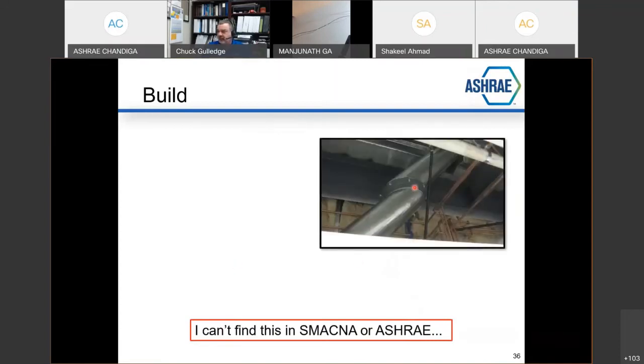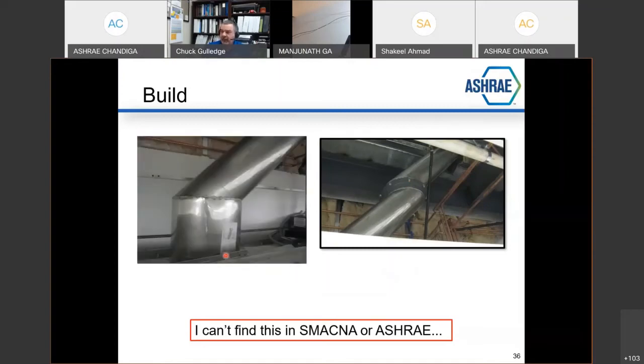I can't find this in SMACNA or ASHRAE. This is special. And yes, that is stainless steel. And would you like to see what it's connected to? That's the back of a fume hood. And look at this brilliant workmanship. How do you even quantify the pressure drop getting air from this hood through the exhaust path to get to the fan? All of this was created by somebody who had the brilliant idea late in the game that instead of the fume hood being located vertically straight down where it was supposed to be, somebody's cabinet layout wanted to modify it. So they moved it in the field, and the plumbing gases for the hood all got reworked, and the mechanical came back and did this. Brilliant. Obviously, we had a problem with flow on that hood.